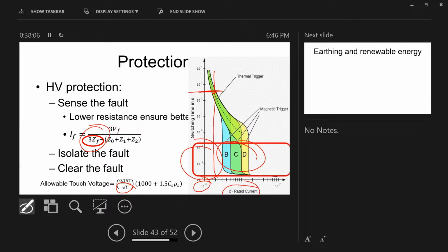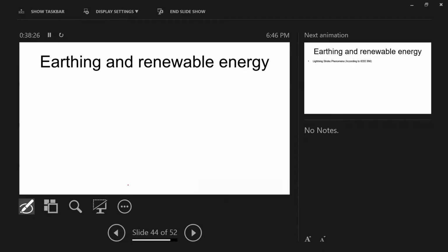I did a job once in the industry where we had a high soil resistivity. We had to get permission to connect the entire town into the earth grid of the substation to lower the resistance and to make sure the EPR doesn't go above the allowable limit. Now, the last item is lightning.